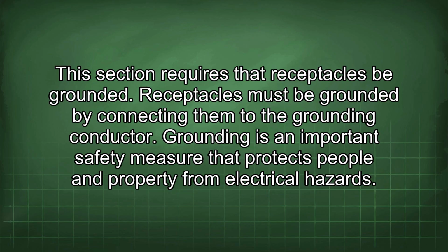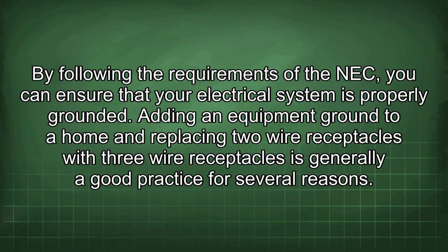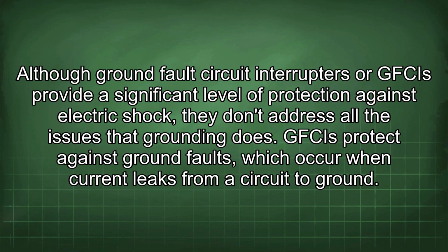Grounding is an important safety measure that protects people and property from electrical hazards. By following the requirements of the NEC, you can ensure that your electrical system is properly grounded. Adding an equipment ground to a home and replacing 2-wire receptacles with 3-wire receptacles is generally a good practice for several reasons. Although ground fault circuit interrupters, or GFCIs, provide a significant level of protection against electric shock, they don't address all the issues that grounding does.